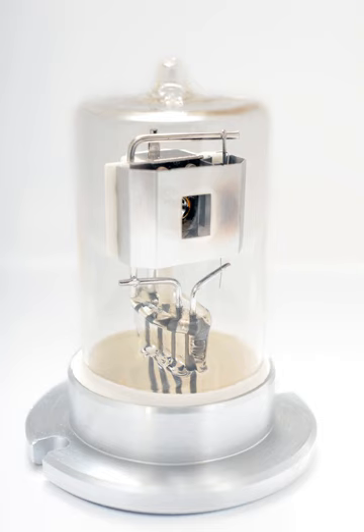The typical lifetime of a deuterium lamp is approximately 2,000 hours. Most manufacturers guarantee 2,000 hours, but newer lamps are consistently performing well at 5,000 hours and more.